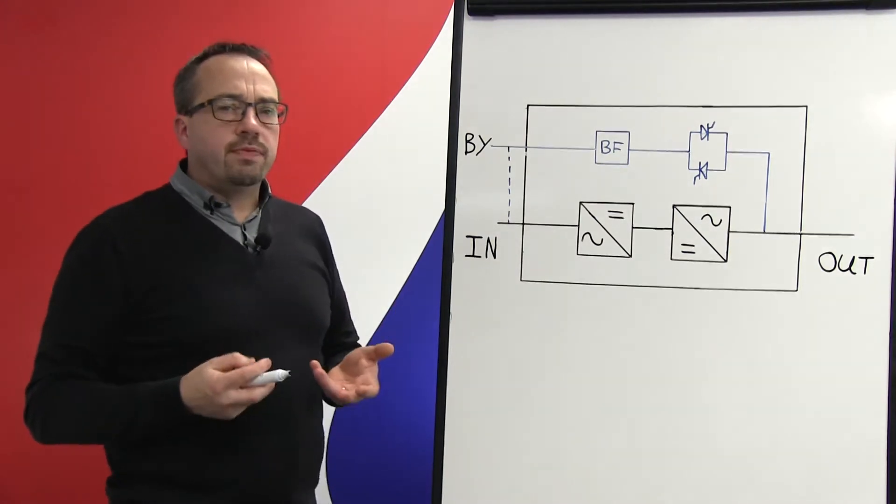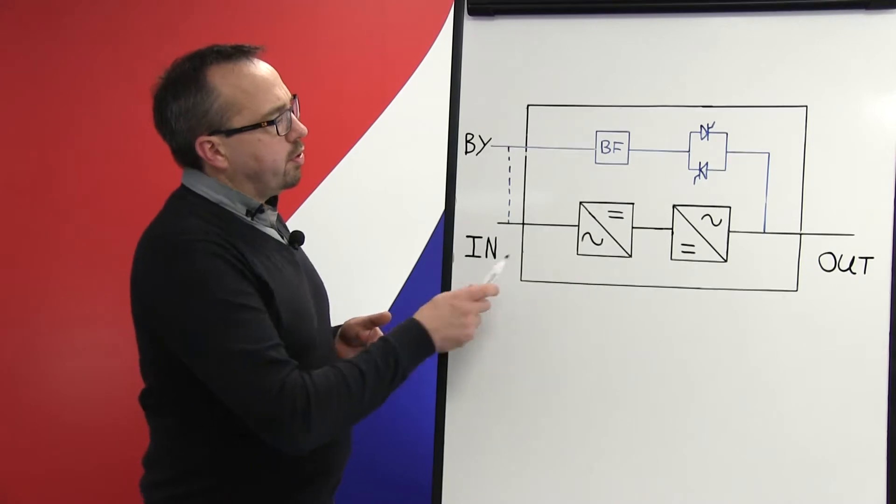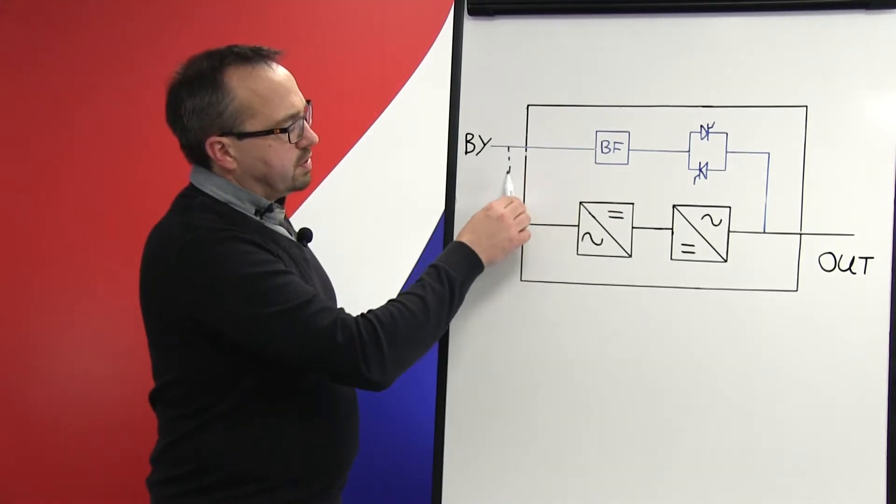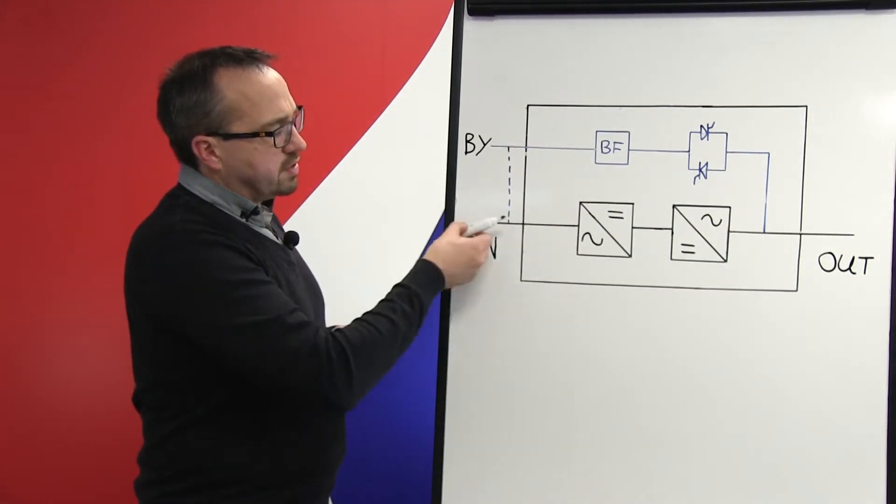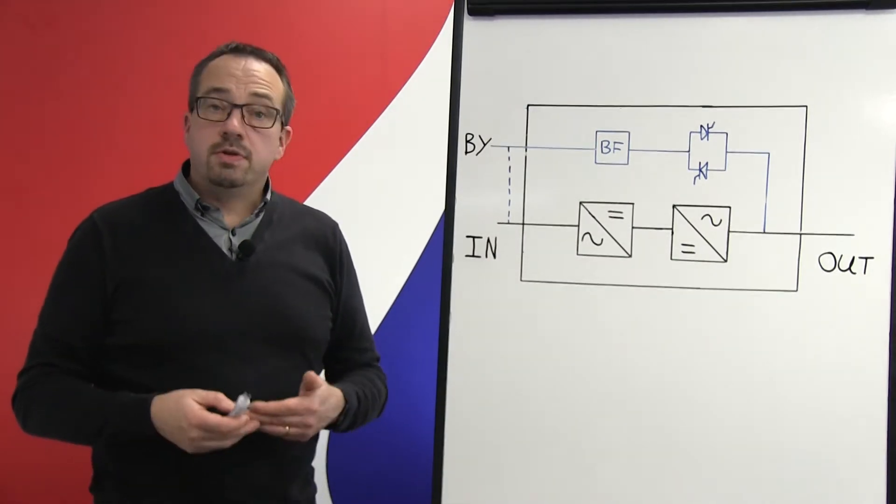Depending on the configuration of the UPS, whether it be a single input UPS or dual input UPS system, will determine whether the bypass supply will either take the power from the same source as the rectifier in the case of a single input UPS, or if it's a dual input or dual fed UPS.